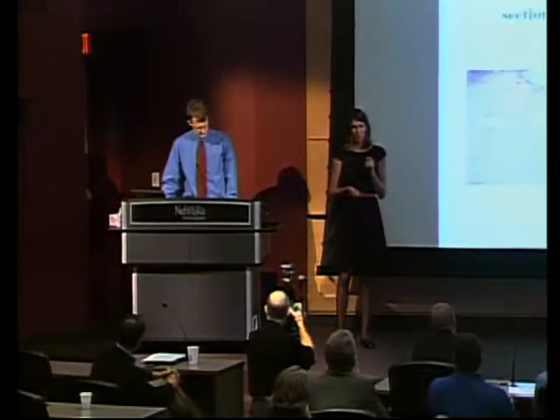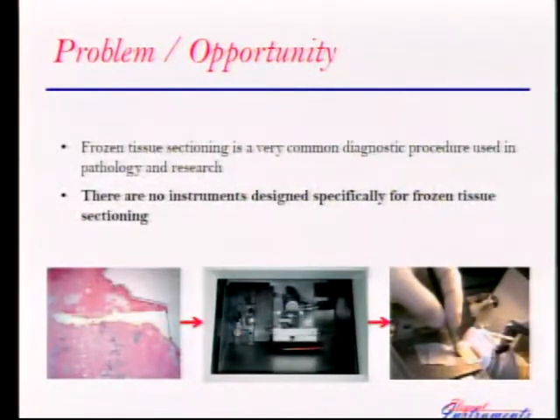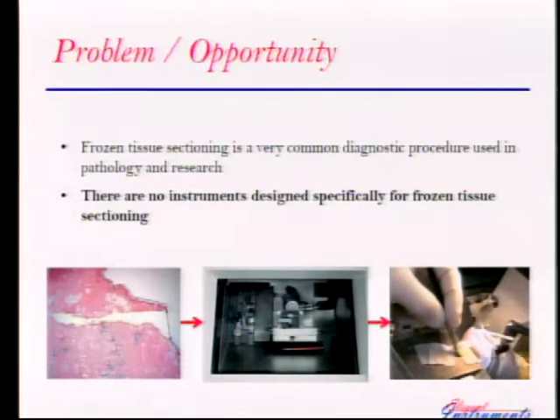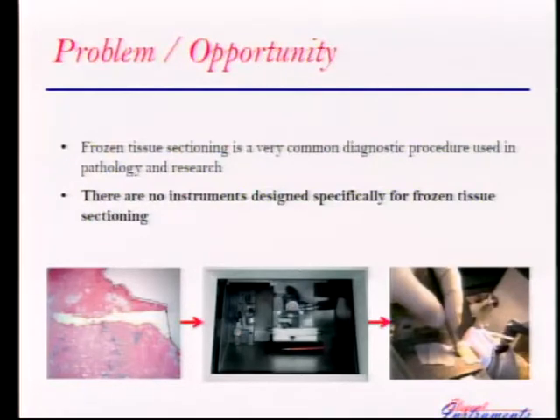Today we will tell you about our first instrument which we designed and developed for frozen tissue sectioning. Frozen sectioning is a diagnostic procedure. One example of when it's used is during cancer surgery. A surgeon takes a small piece of tissue from a patient, freezes it, and sections it very thinly. Those very thin sections are put on a microscope slide and observed to see if any cancer cells remain. A cancer tumor can regrow from one cell, so it's very important.